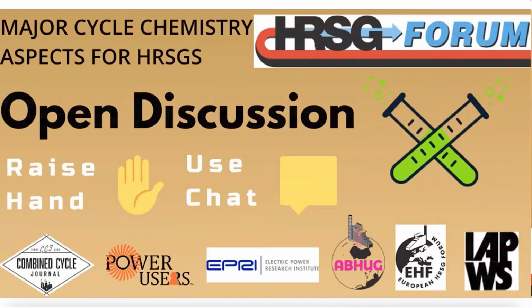Yeah, Matt, thanks very much. And the short answer is, I think I've talked to you about it before, that you can go to the IAPWS document on deposits in HP evaporators, but there's basically three things that we like to do. The first one is to make an understanding of the deposit loading, and there's an ASTM procedure for that. I can't remember the number, but it's in the IAPWS document.